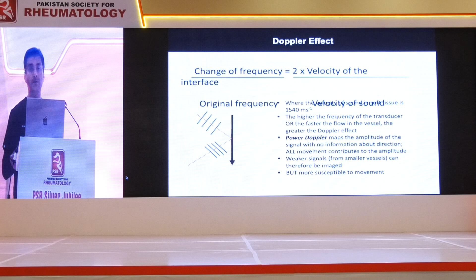But essentially, if at the end of that whole process, you still have an ugly image, it still doesn't look right, change your probe. Change your probe and go to one level down. So if you're starting on the 18 megahertz, go down to the 12, and start this whole process all again. Make sure your preset is correct, make sure your contact is good, gain, depth, focus, anisotropy. Image is still bad, change the probe again.